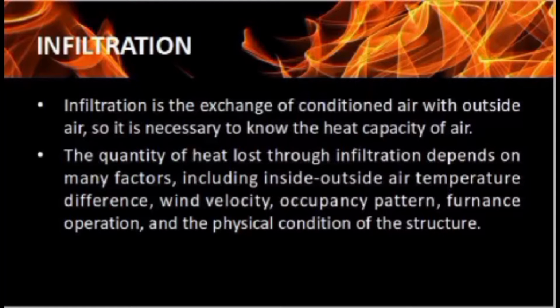The quantity of heat loss through infiltration depends on many factors, including inside-outside air temperature difference, wind velocity, occupancy pattern, furnace operation, and the physical condition of the structure. Wind is one of the factors kasi yung wind nagre-create ng pressure within the building dahil dito nag-i-increase yung infiltration rate. So habang lumalakas yung hangin, the amount of air leakage will increase.